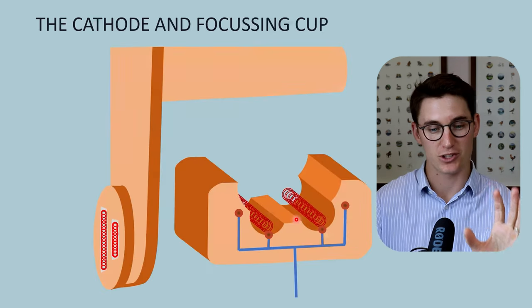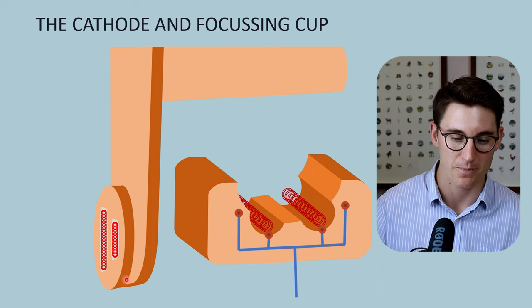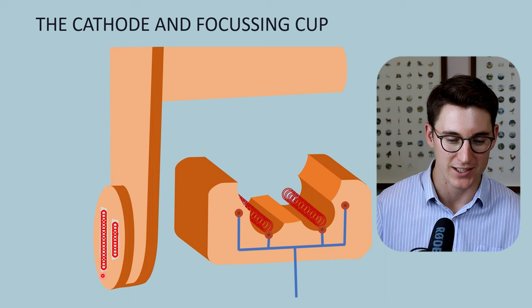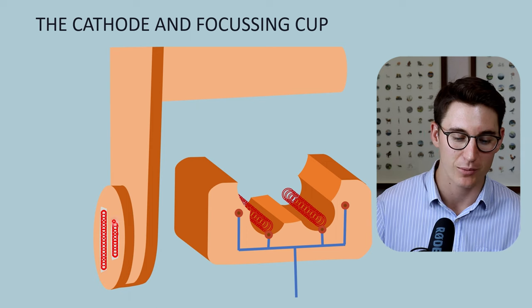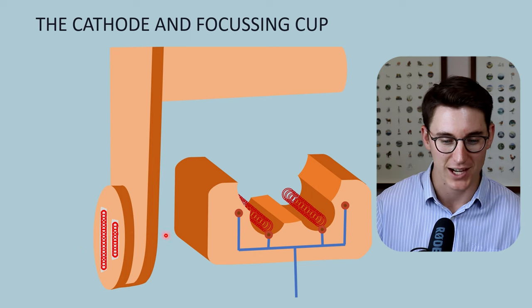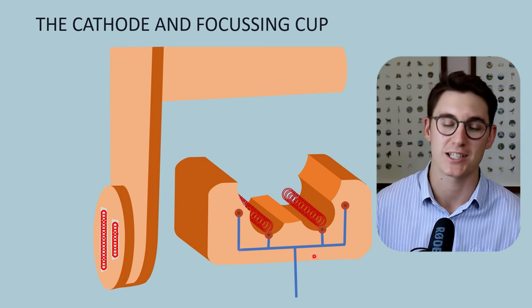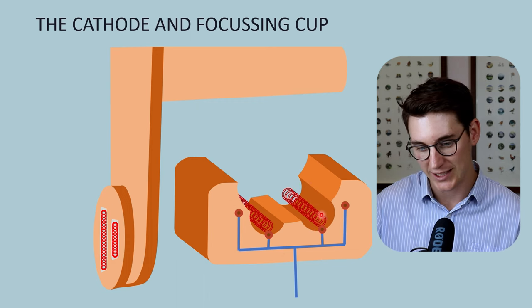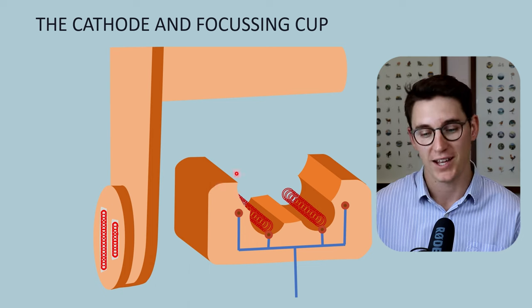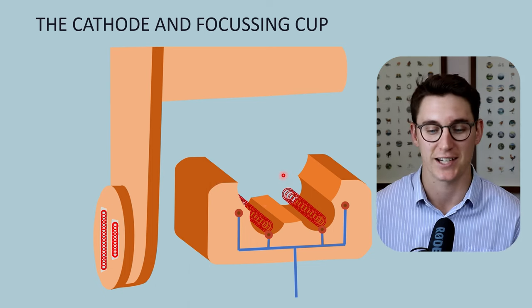If we tilt this cathode slightly and look at it front on, we can see the face of the cathode. The cathode is negatively charged and within its face there are two tungsten filament coils that have been machined into the face. If we were to cut this cathode in longitudinal section we would get this cross-sectional view. You can see our tungsten filament coils within the cathode itself, and this concavity here is what's known as a focusing cup, which we'll look at in a second.